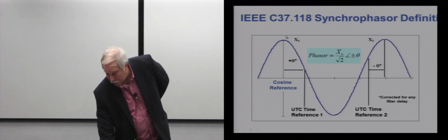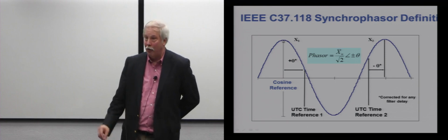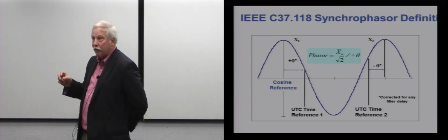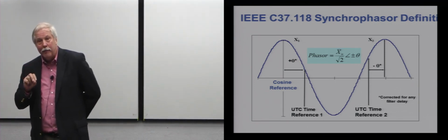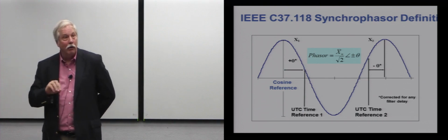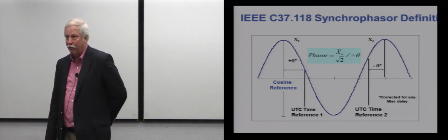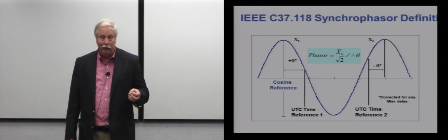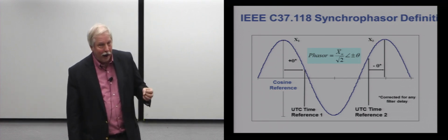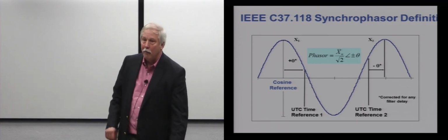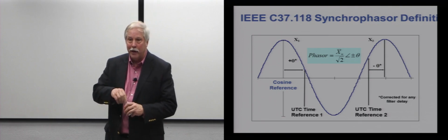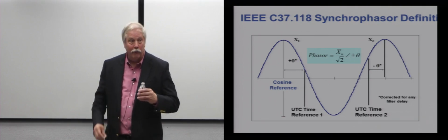That is the absolute angle of a synchronized measurement. That measurement point also has a peak of the fundamental waveform. The synchrophasor only looks at the fundamental frequency. It does not look at any harmonics in the waveform. In fact, the standard says that you shall reject any harmonic measurements from any synchrophasor measurement.